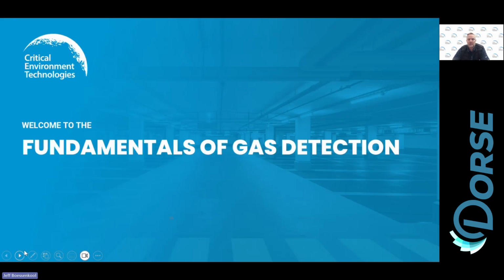Okay, so we've talked a little bit about the types of hazardous gases already. Just want to talk a little bit more about that quickly. Toxic gases typically measured in ppm, parts per million, sometimes ppb, which is parts per billion. We can get that specific. We've already talked about CO and NO2. Ammonia is another one. Ammonia used for chillers, for ice making machines, ice rinks, curling rinks, and other applications. Very toxic gas. Matter of fact, there's 3 people that lost their lives as a result of ammonia overexposure in British Columbia about 8 years ago, right? Very toxic gas. Chlorine, another very toxic gas.